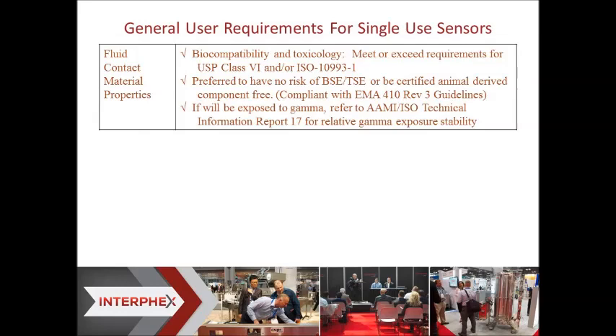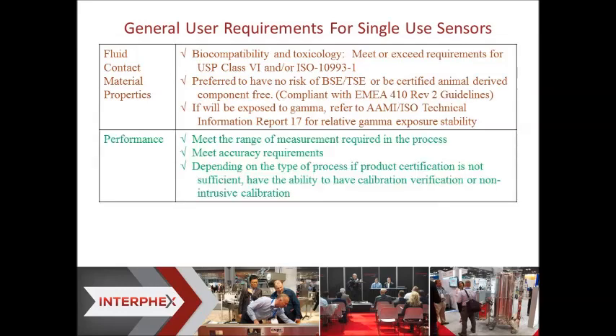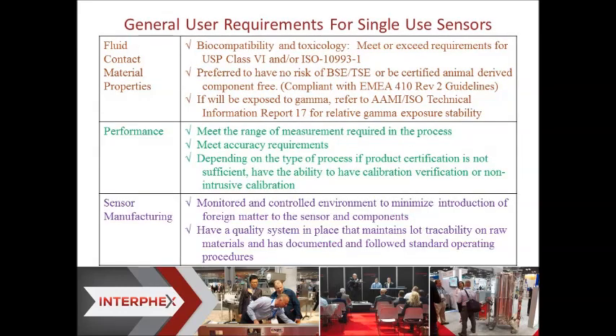As far as fluid contact materials, this is relevant to any material, even something like tubing. You want to make sure the sensor material has the correct certifications. As far as performance, you need to determine the range of measurement required in the process, what accuracy you require, and, depending on the type of process, what type of certification you may need with the sensor to use it. In terms of the sensor manufacturing environment, this goes from the manufacturing environment right into your process. You want to make sure sensors are manufactured in a clean, controlled environment to minimize the introduction of any foreign matter to the sensor and sensor components, and also that the manufacturing facility has a quality system in place.